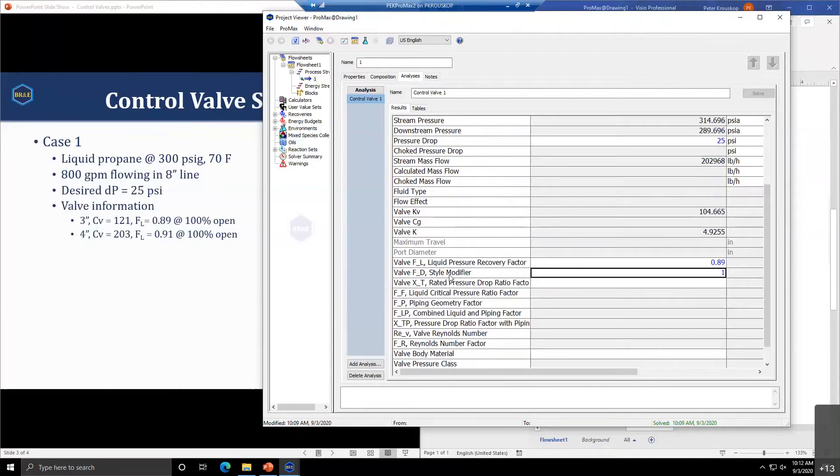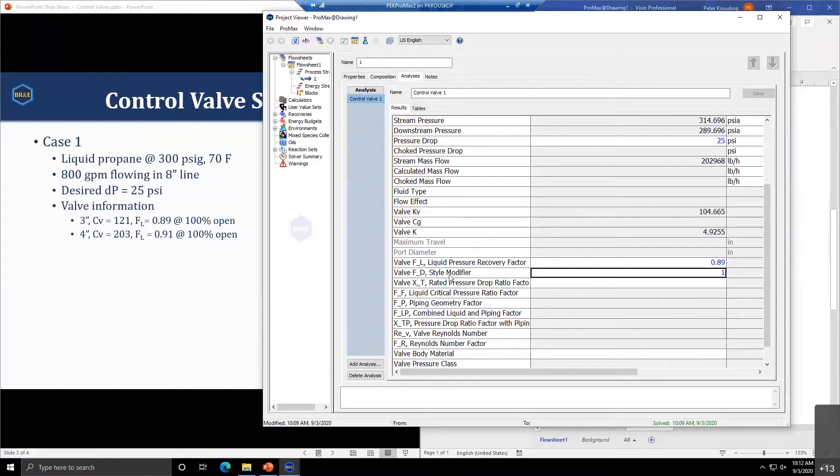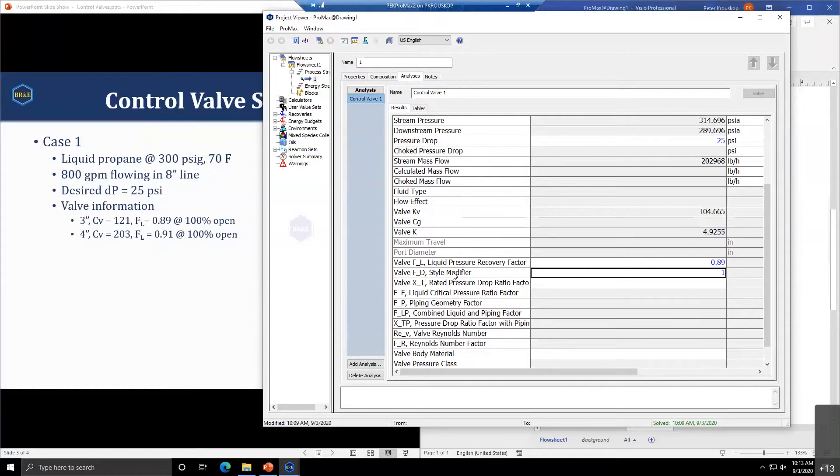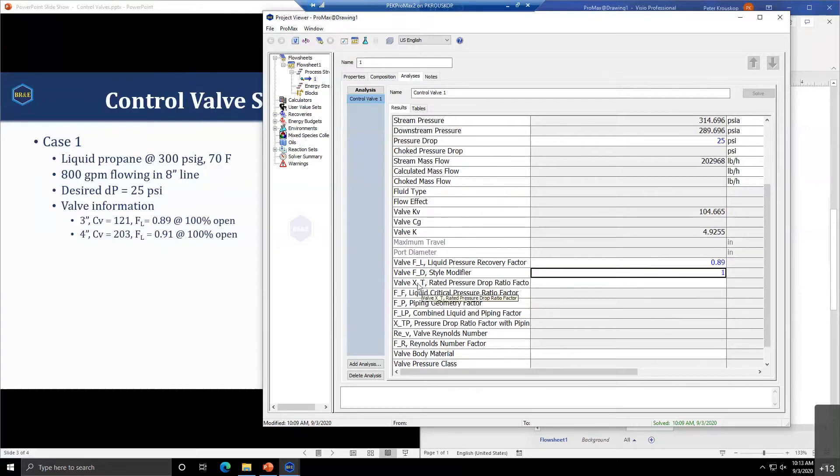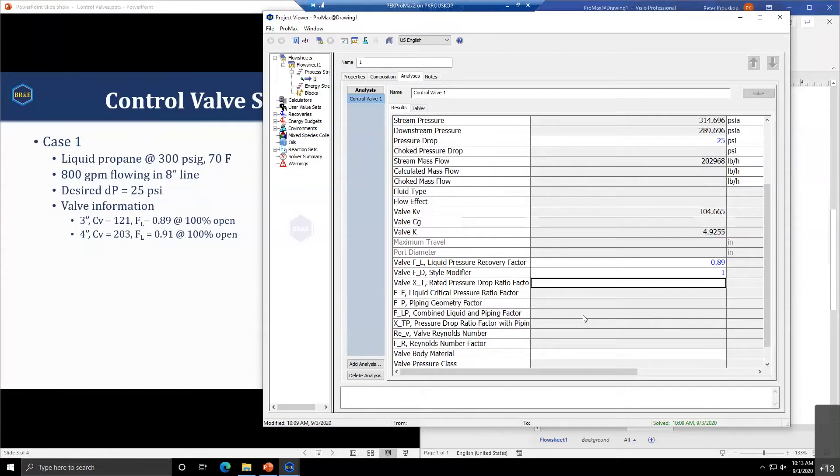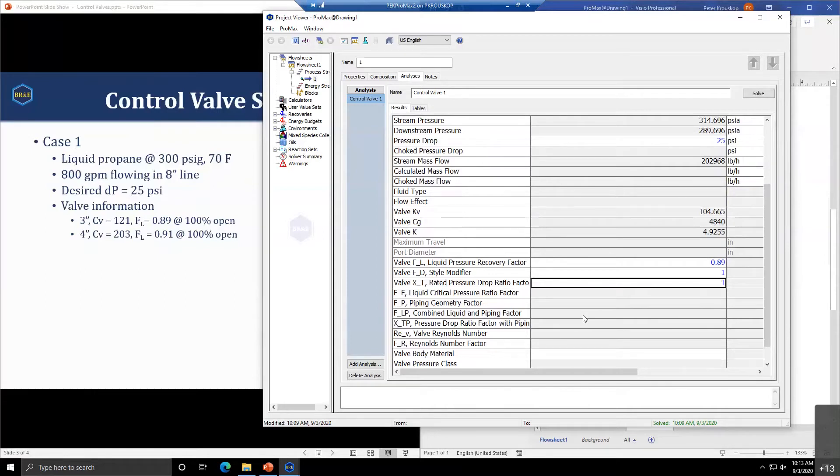We want to obtain a 25 pound pressure drop across this valve. We need to provide the liquid pressure recovery factor FL, which is 0.89 for this valve.